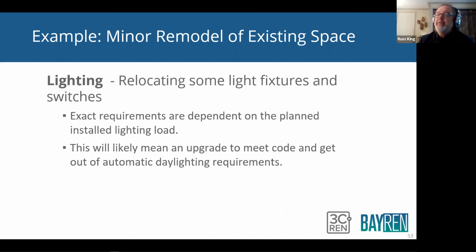So they say, okay, this is a retail space. We're allowed to have a certain watts per square foot. Are we going to beat that? Okay. And you have to beat it. You have to be at least below the lighting power density. If you're just below the lighting power density, you're going to have some special switches. But if you can beat it by 20%, you don't have to have as many controls.